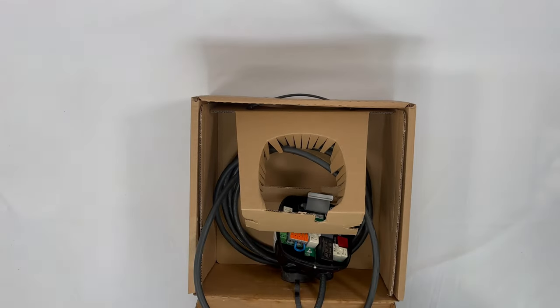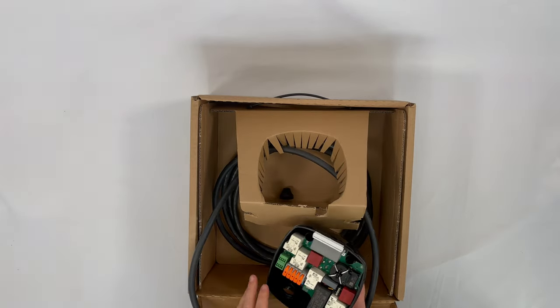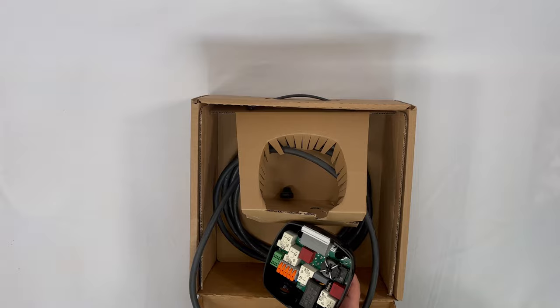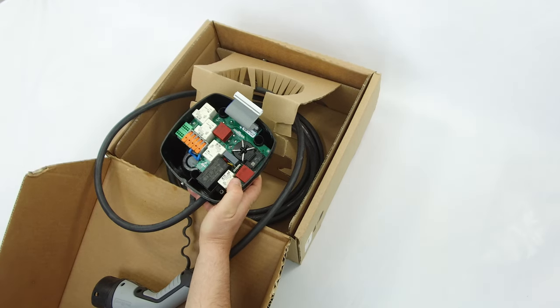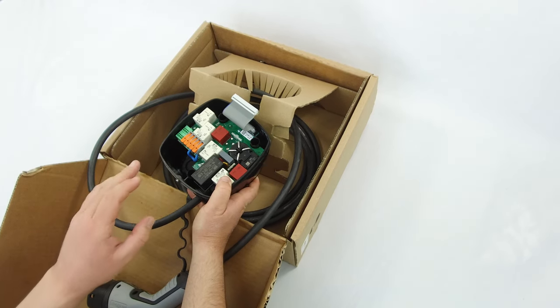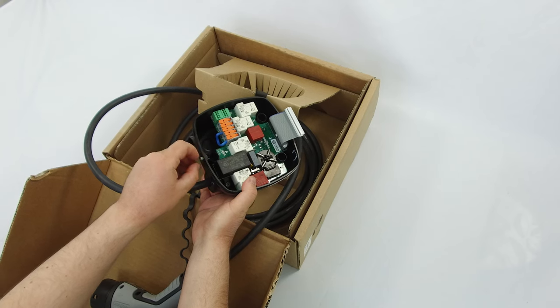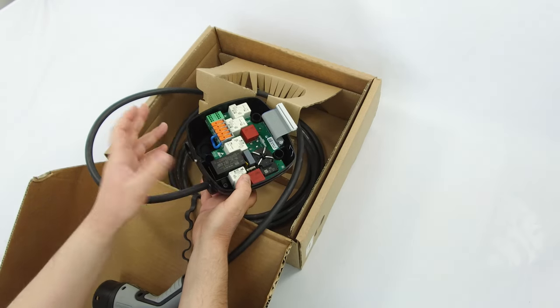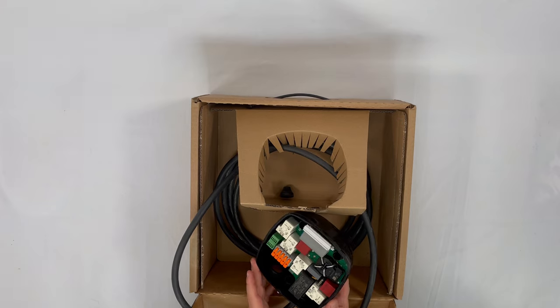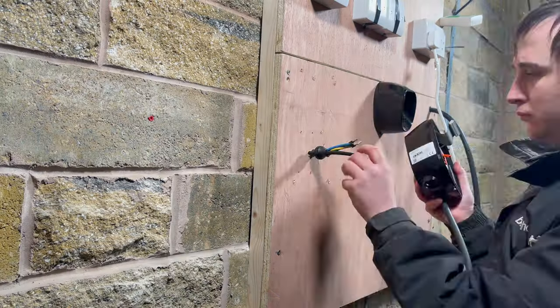Overall, really nice unit inside. Regarding the tool-less clip design, a few engineers have pointed out it may impact IP ratings, and a couple have commented that screw terminal units with torque screws at the front would be more waterproof. The only screw on this is a small torque screw at the bottom just to prevent vandalism. Personally, I prefer not having a million screws at the front that could be incorrectly torque-tightened — just a push-on clever design like this.